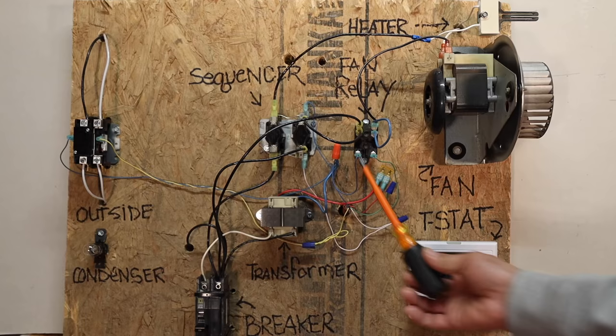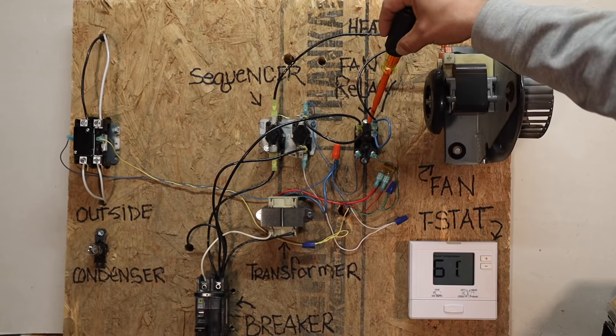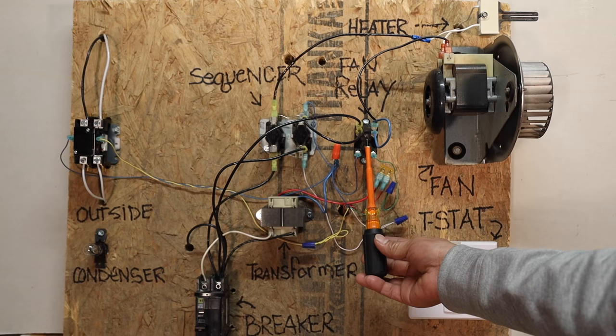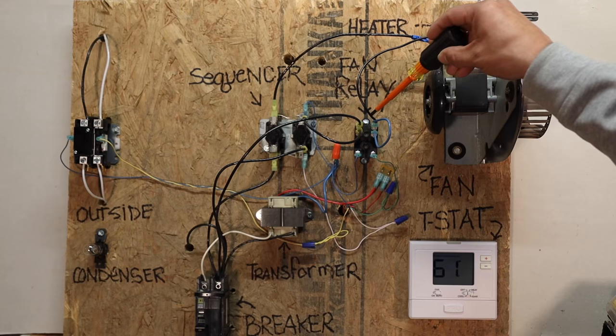These two top spade clips are what they call normally open, so they're broken right here. But when this has 24 volts applied to it, this piece of bimetal then pushes up and passes power from this side to this side, which then will energize your blower motor.